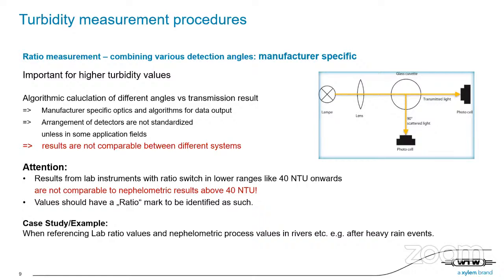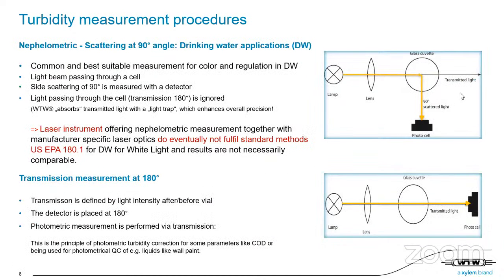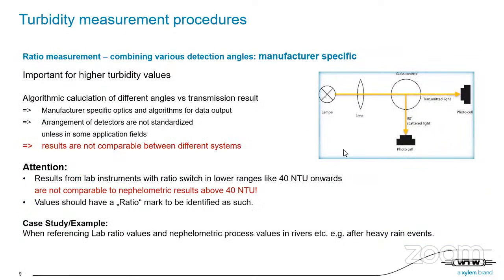And this makes it clear that a ratio measurement is never the same value as a nephelometric measurement, because with nephelometric we do not have a second detector and we do not have a calculation between two different angles. Why am I telling this so heavily? There are many meters which start to read ratio, so with two or several angles, above 40 NTU. And for drinking water, the regulations go up to 40 NTU.